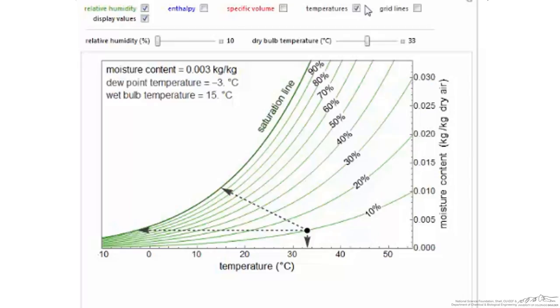The wet bulb temperature is obtained by following the same lines we used to evaluate the enthalpy. These lines are called adiabatic saturation lines. Follow this line until it hits the saturation curve and then drop a vertical to read the temperature. For this case, the wet bulb is equal to 15 degrees C.